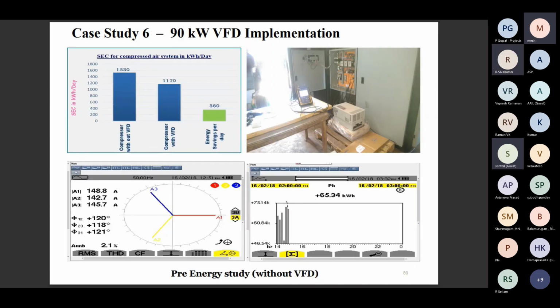Next, another example is a 90 kilowatt VFD implemented on one compressor. There is 70% loading and 30% unloading. Actually, 65% is loading and 35% is unloading. Once it is retrofitted, they can save 360 units per day.